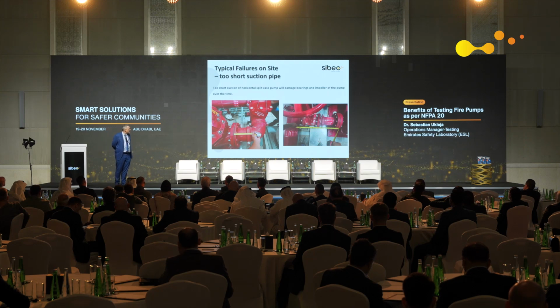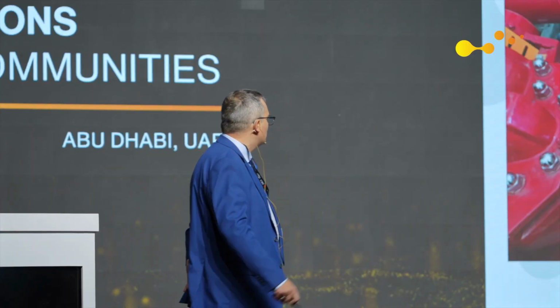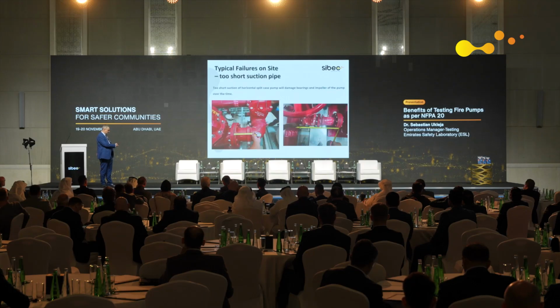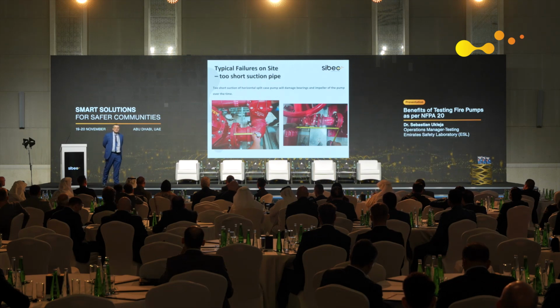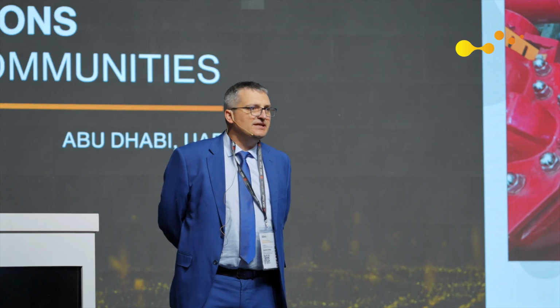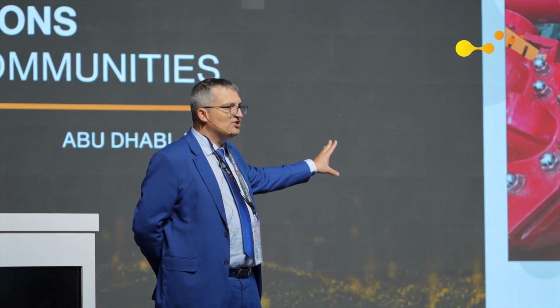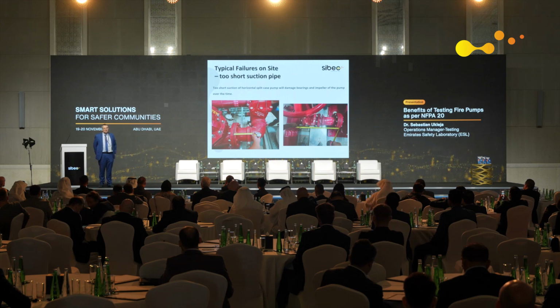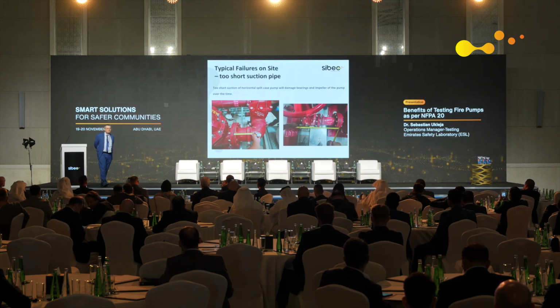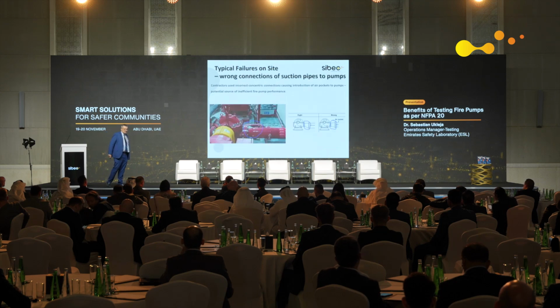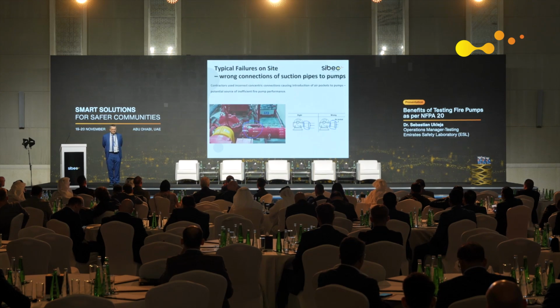Another problem which can happen, and it will kill the pump over the years, is too short suction, which is not according to NFPA 20. In a nutshell, sorry, I'm just mixing the next slide with the laser. This should be 10 diameters of the pipe, which we're talking about 1.5 to 2 meters length. What is happening? The imbalance of the pressure is killing the bearings of the pump. So the pump will perform initially very good, but over time, the bearings will be gone. And we get the situation that the pump will not be operational at all. And this situation is, unfortunately, quite common.